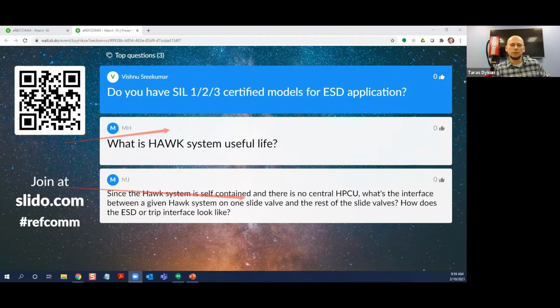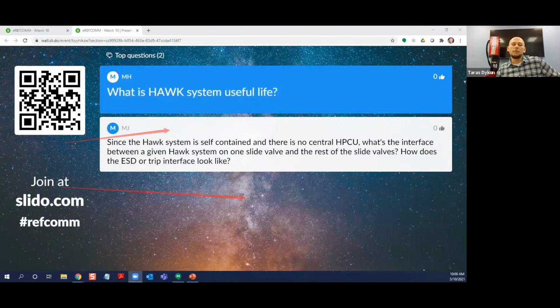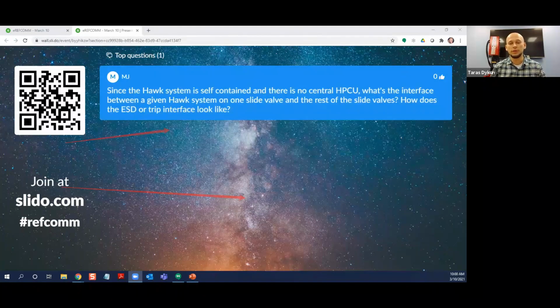What is the Hawk system's useful life? Usually we talk about 20 years. But you need to rebuild the units and change the soft kits every 5 years. So basically change the pump, the seals, and the solenoid valves. Every 10 years you would have to go through a full rebuild, probably replace all this little red box and the control components. But you should expect these units to run for about 20 years, though of course you will need to do the maintenance.